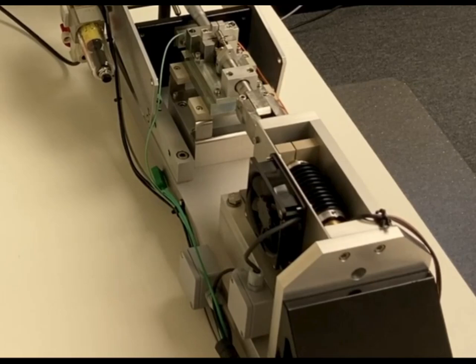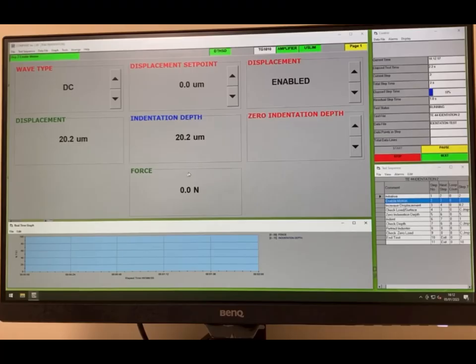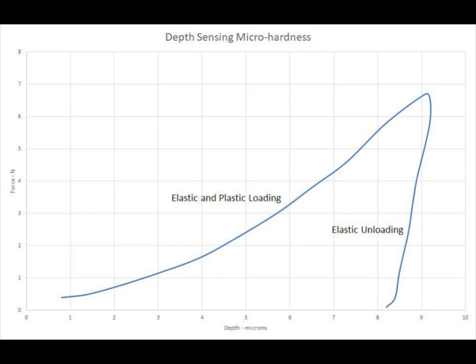To run a hardness test, the user starts by entering the required indentation depth. The test sequence then automatically moves the indenter by small increments until the surface is detected. This is indicated by a rise of 0.1 newtons in the indentation force. When the surface is detected, the indenter displacement reading is automatically zeroed. The indentation is then performed.